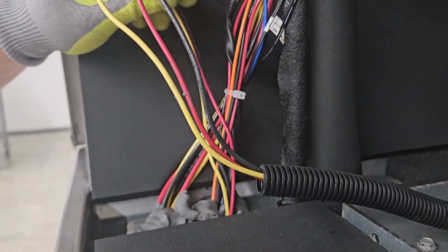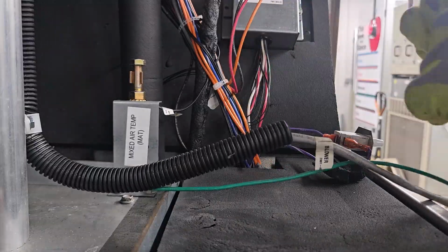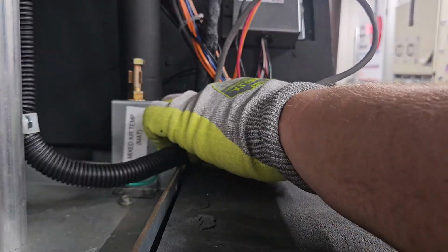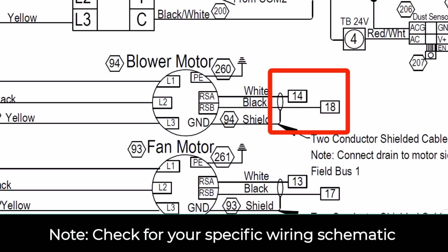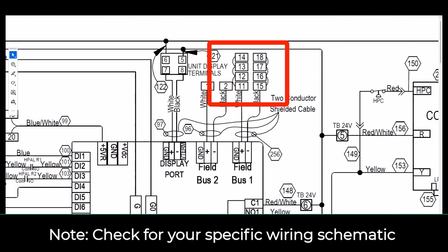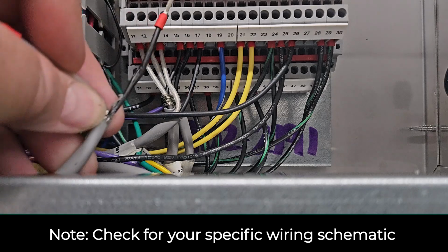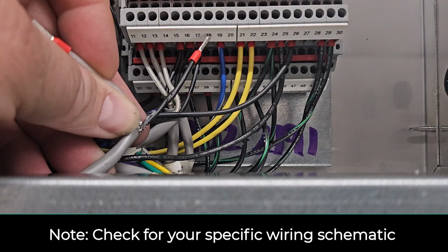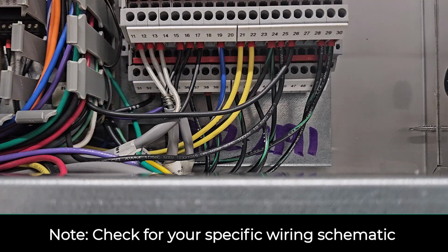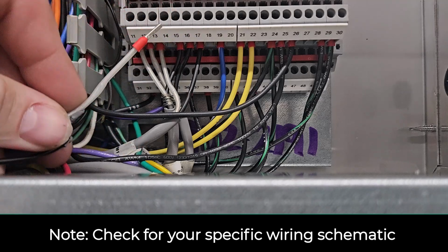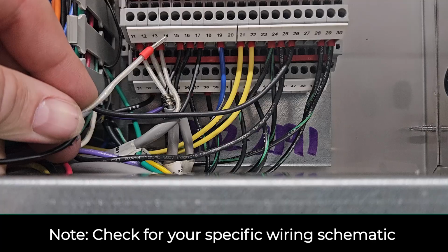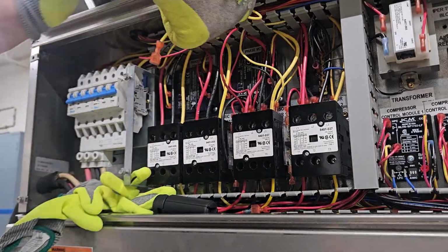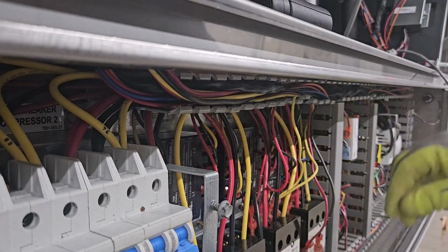Route the high voltage wires from the fan assembly into the electrical compartment of the MEGA-TEC. Route the communication wire and the grounding wire to the electrical compartment. Check the schematic drawing for the appropriate terminals to hook up the Modbus communication to the terminal block. There are multiple devices that are using this communication, and they are all connected by jumpers on this specific terminal block. Hook the high voltage wires to the correct contactor on the unit.